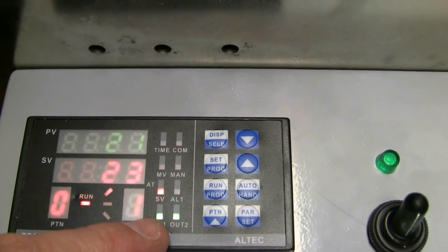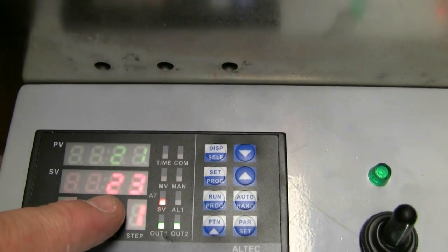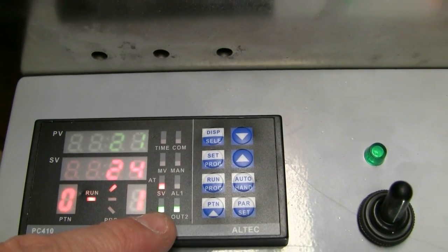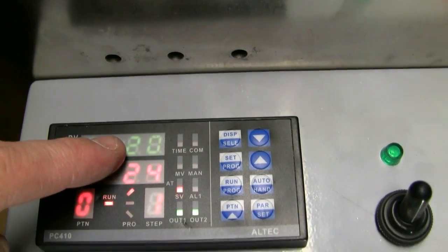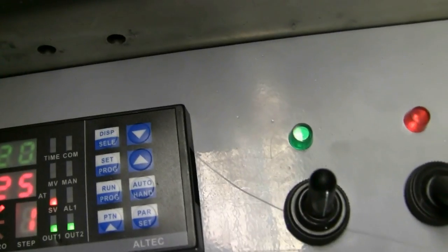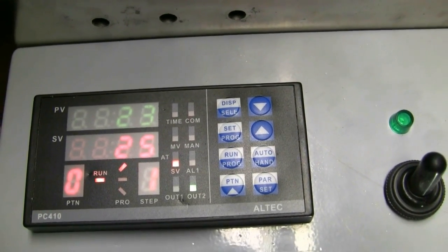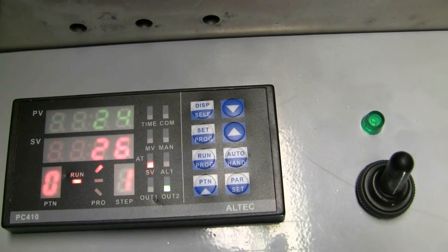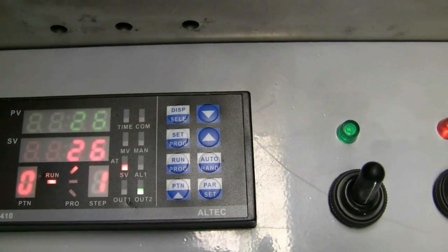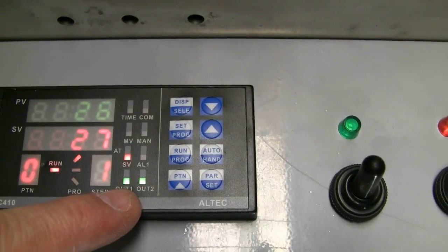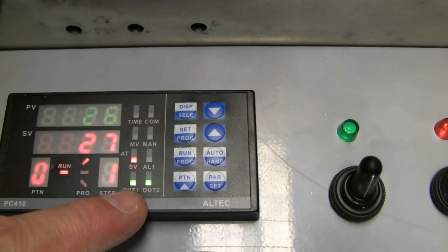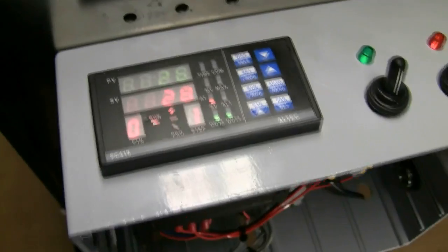There's no heater, so what the controller is basically doing is saying turn the heater on because my set point is two degrees higher than my actual temperature. As soon as I raise the heater value to approximately the set point, now the heat has gone off. And as the temperature drops, the heater comes back on again. It's clearly working. It might not have quite the right PID values, but it's operating as a thermostat.